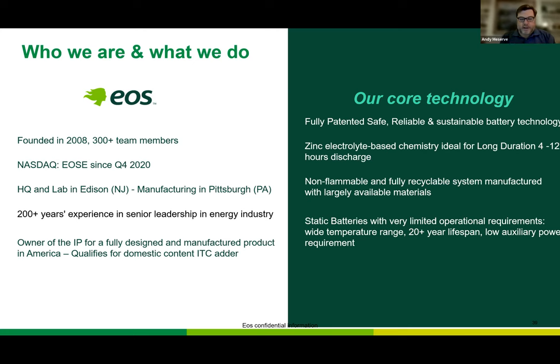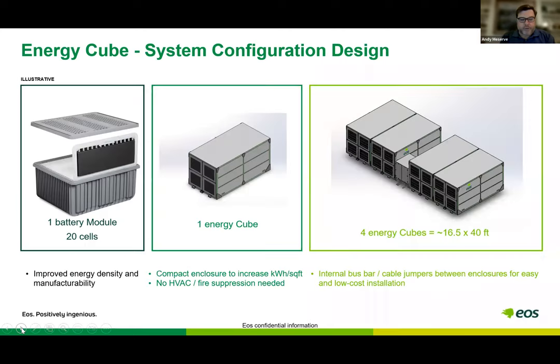Next slide, please. We'll show you how we configure the batteries. One battery module is a sealed plastic tub with 20 cells containing the aqueous solution, which we have a lot of patents around. That sealed battery goes into an energy cube, and we do all the wiring in parallel series. Those energy cubes are put together into roughly a 40-foot container configuration, about 2.5 megawatt hours. All the wiring comes into a marshalling box, so it's very easy for installers and contractors to attach the DC converters, the PCS, and things like that.